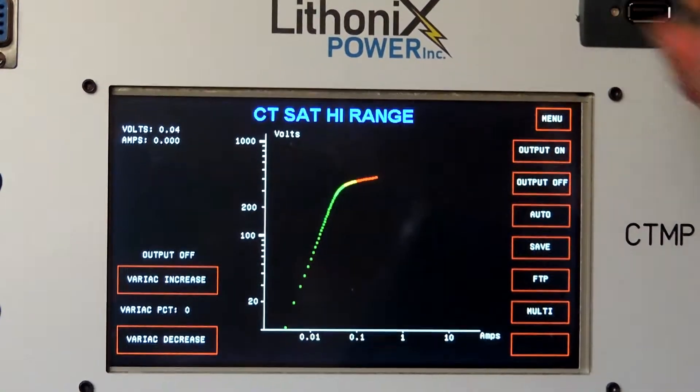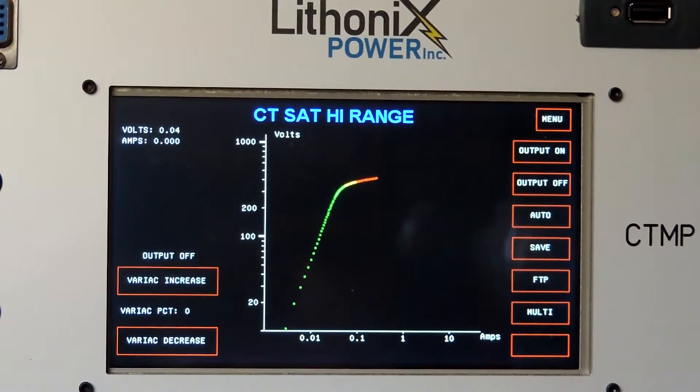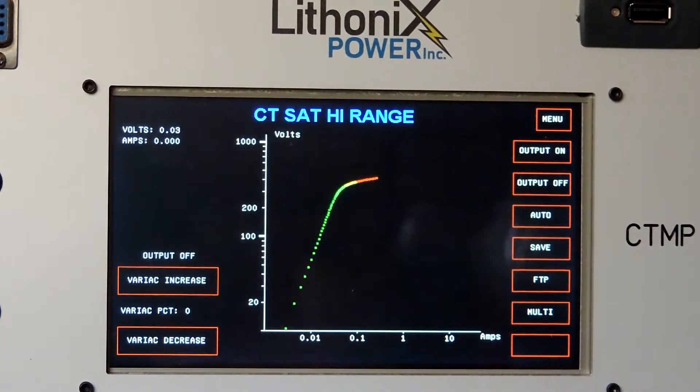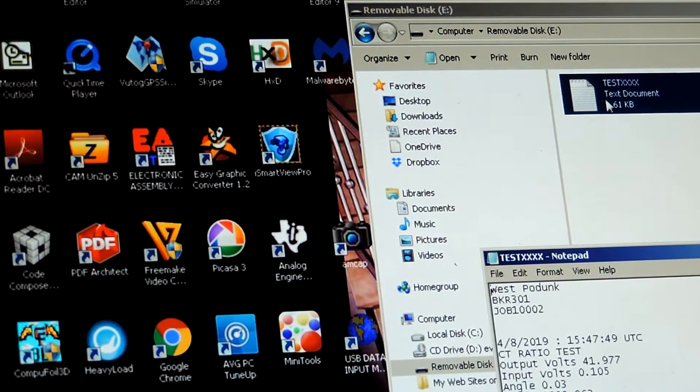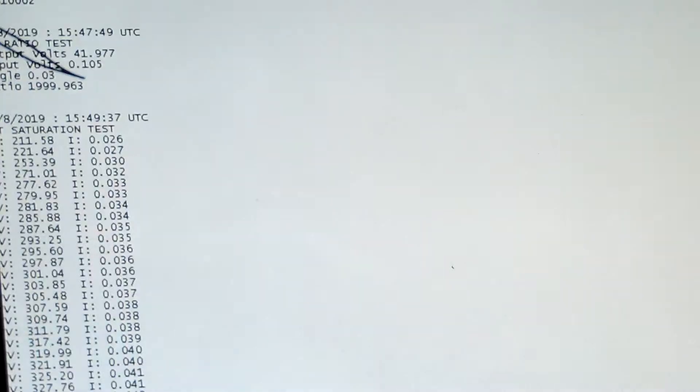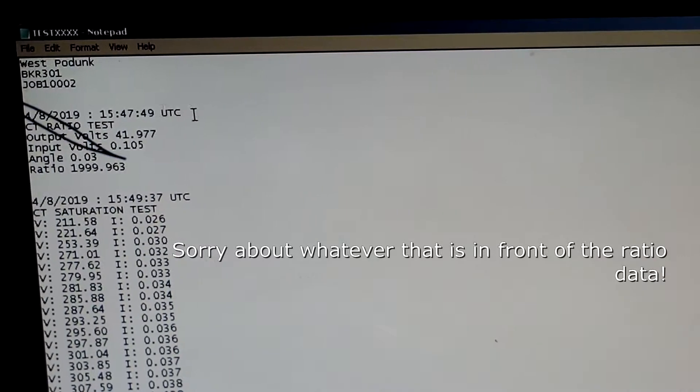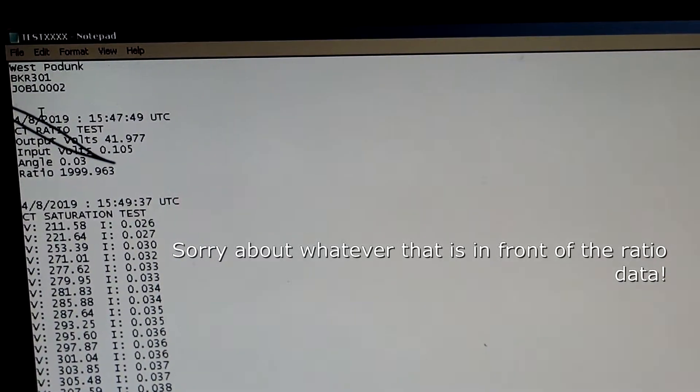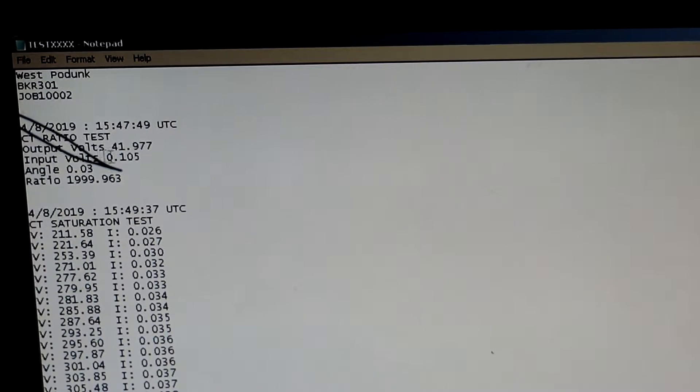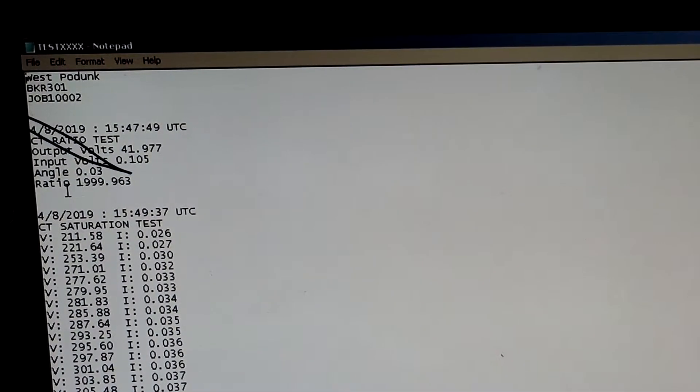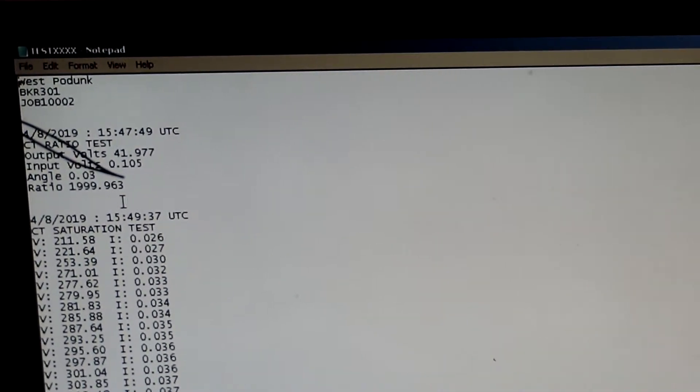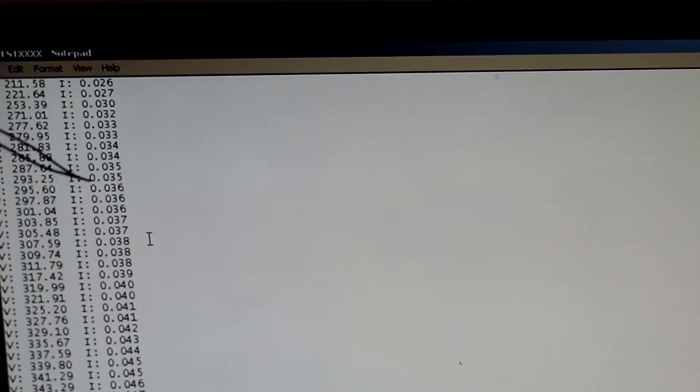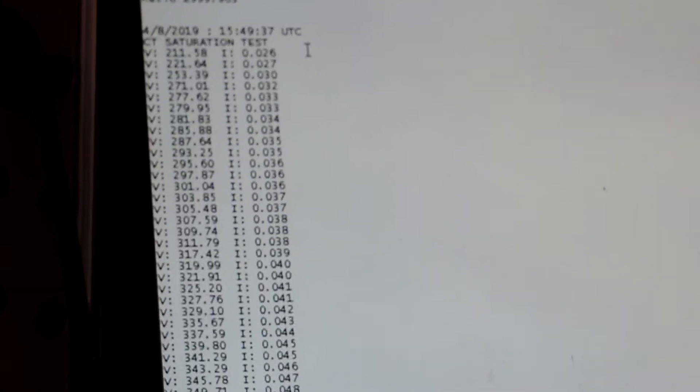I'm going to remove the drive from the test set and put it in the PC. Pointing this at the file here, and you can see that I have the substation info which it did download from the internet, I have the time, the CT ratio test output and input voltages, the angle error, and the ratio to 5, which was 1999.963. And then it has the saturation test data below that.